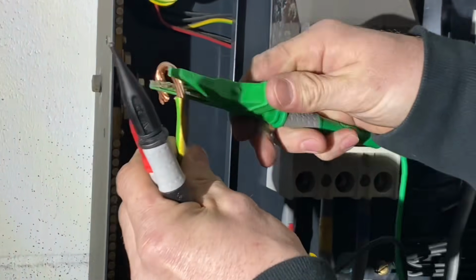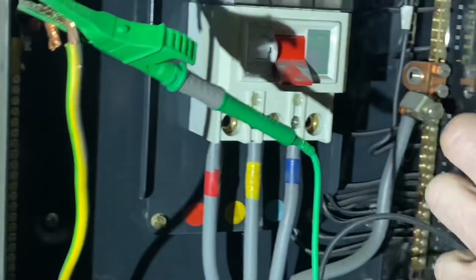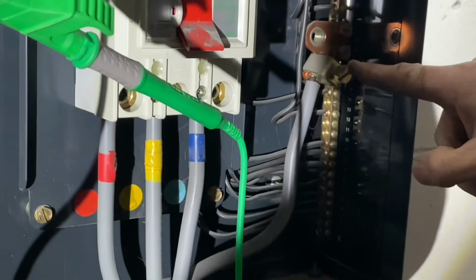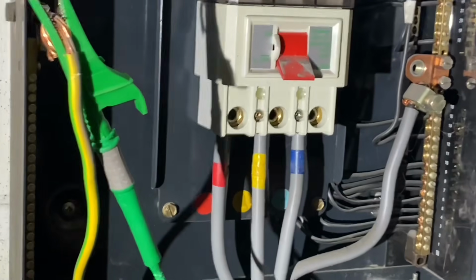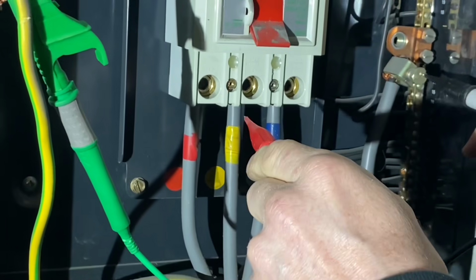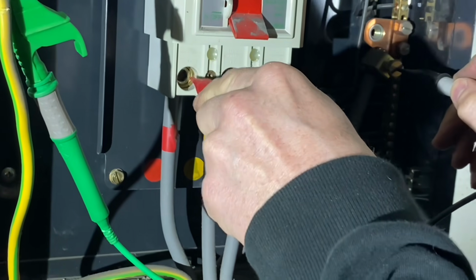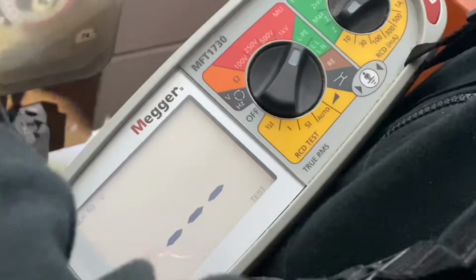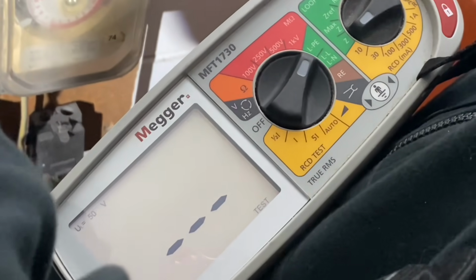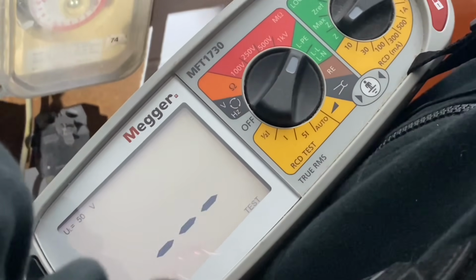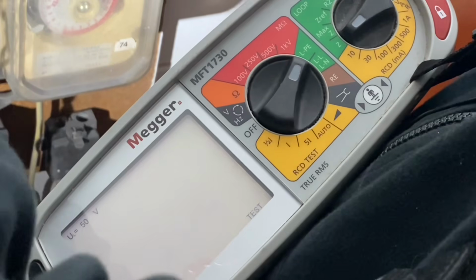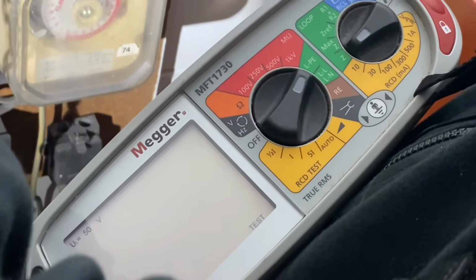Right, okay, do you want to probe on for me so we can see? So we've got the exposed disconnected earth there, so we'll get a good connection onto that. Then we've got the neutral terminal here, and then our three phases there. So let's move that one out of the way. Again, it's an automatic test. So go onto the neutral terminal first, and then we'll probe onto the first line conductor. As you can see, the machine has automatically detected voltage, and it takes a few seconds. Because we're on the low setting, that's fine. So we'll persevere and wait for our result.